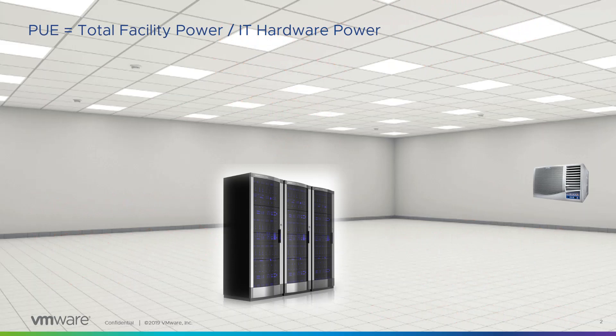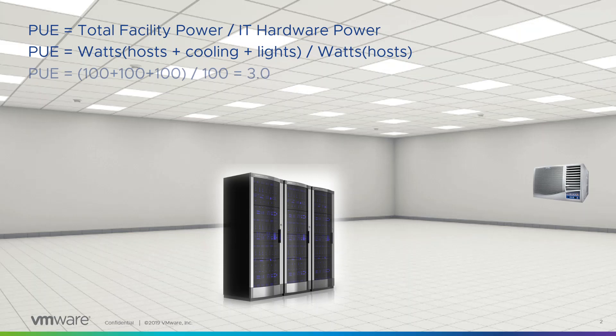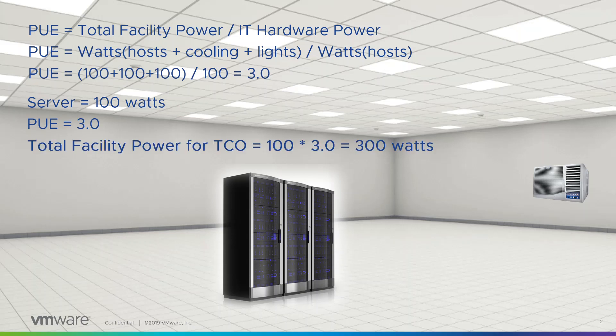To calculate the PUE, we take the total facility power divided by the IT hardware power. In this case, we have the wattage for the hosts, the cooling, and the lights divided by the wattage for the hosts. That's 100 plus 100 plus 100 divided by 100, which gives us a PUE factor of 3.0. So if we know the server takes 100 watts and our PUE factor is 3, then the total facility power for our TCO will be 300 watts.